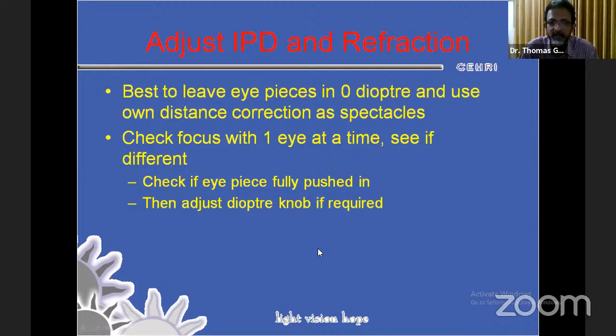But in between, look in the distance. It's very easy to accommodate while you're doing this. So in between, keep staring off at the wall and then look back and see if it's okay. Adjusting the IPD, it's best to do it with both eyes open. Widen the IPD till there are two circles seen. Slowly bring the eyepieces close together till you see one fully illuminated, complete circular field. There should be no shadows in that circle. And this is seen with both eyes open. Look away in the distance to make sure you're not accommodating.